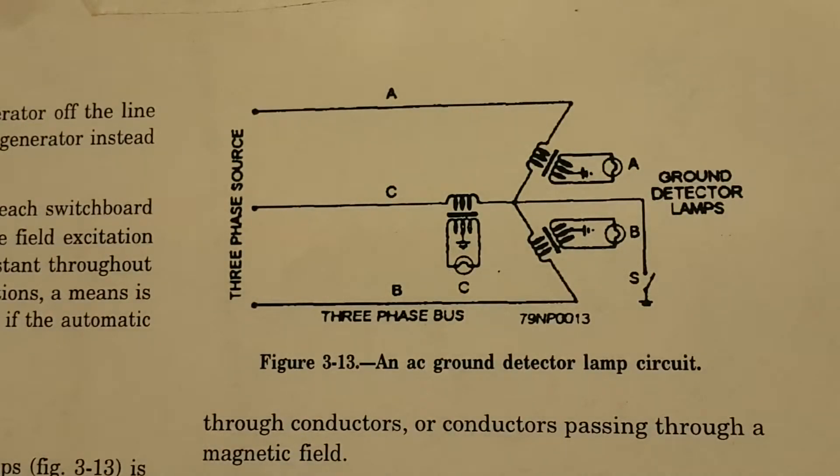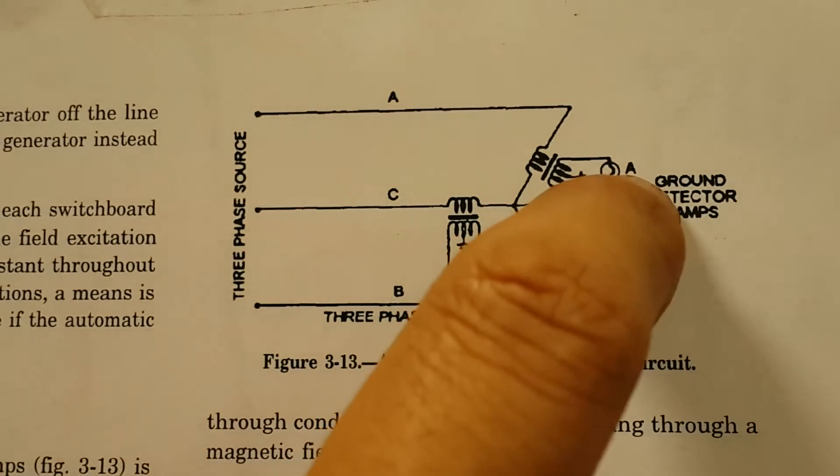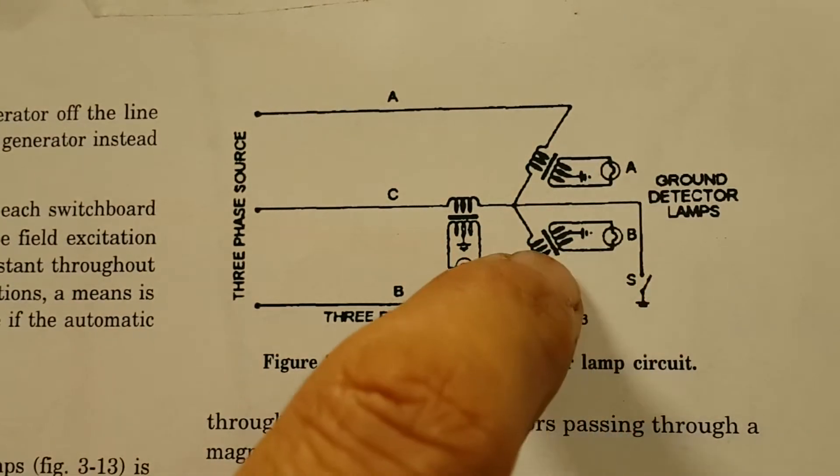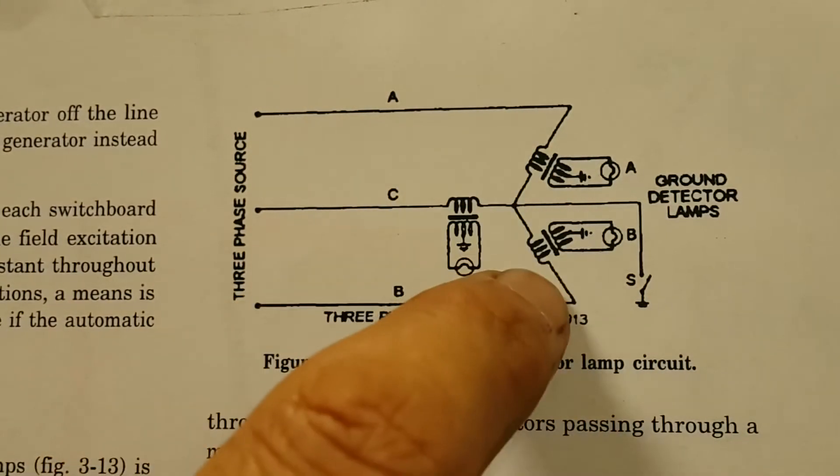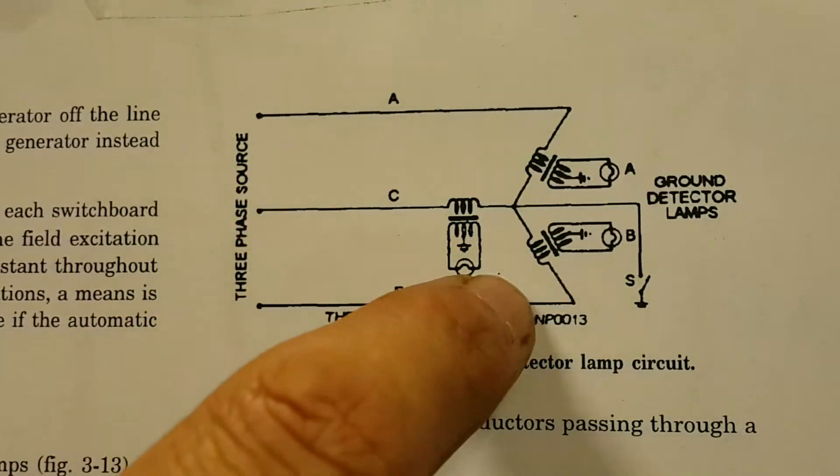Here I got the electrical schematic from the ground detector lamp circuit that I just showed you. Each lamp is attached to the secondary of the isolation transformer that we have there. And then this is the push button over here that is connected to the center. The lights are connected in Y, as you can see.